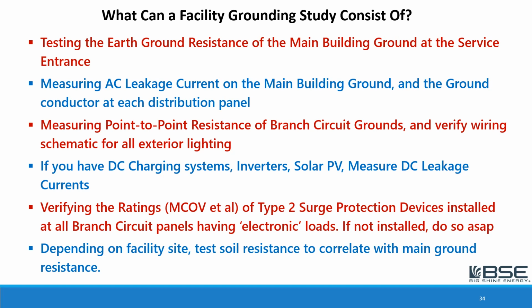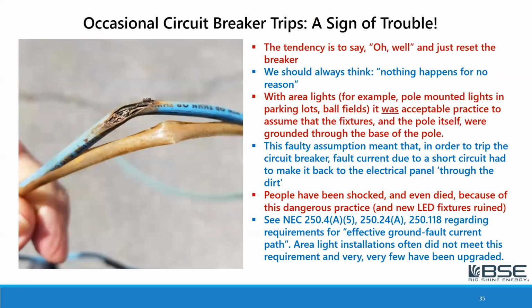And then depending on the facility, you can also test soil resistance to correlate it with your main ground resistance. Now, we find all kinds of problems out there when we do sustainability upgrades at facilities. Very often there's been a problem, but nobody really recognized it as a problem. But then when we install brand new equipment, if there's some kind of an issue, then it kind of comes out: oh yeah, we did have a problem now and then.